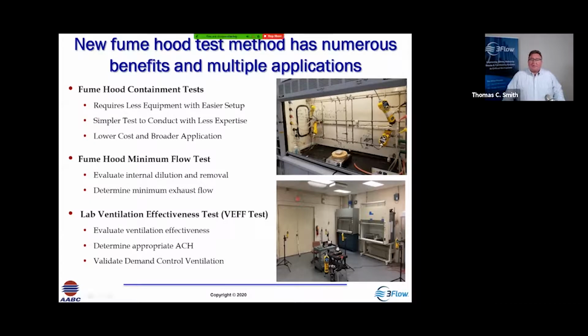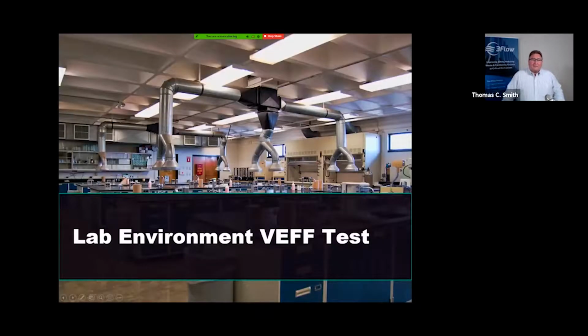And so we can test it. We can put a tracer gas in the lab and determine how effective is the lab at removing concentrations. And that test can be conducted not only in labs, but it can be conducted in offices and conference rooms and all kinds of different environments where people may be congregating, and we want to make sure that they're not going to be exposed to an aerosolized pathogen. So that comes to the Lab VEFF test. So we've tested the hood, we need to look at the lab.